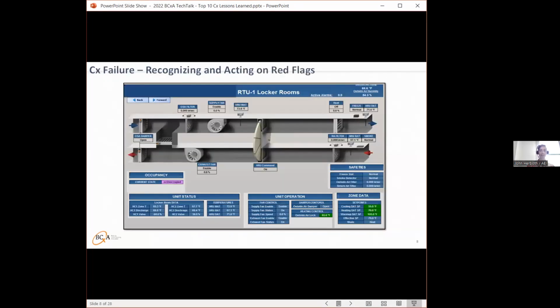So here's a little screen graphic. This was another little red flag to me when I do functional testing, and that is that this equipment doesn't match how it's oriented in the field. That's definitely something I do now automatically when I show up on site, or before, if I get remote access. If I start seeing graphics that are more like boilerplate and not matching how the field equipment is oriented, whether it's the fan location, where the coil is located, or where the sensor is located, I hone in on that really fast.